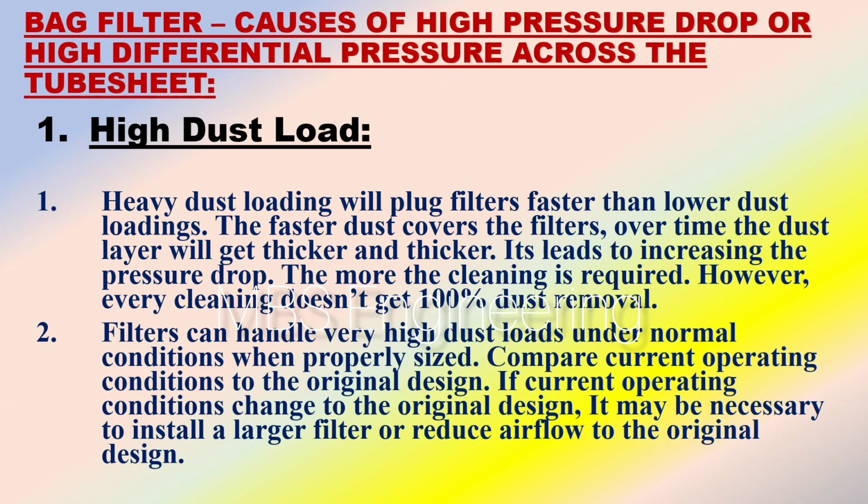One of the main causes of high DP is the high dust load in the gas flow. Point number 1. Heavy dust loading will plug filters faster than lower dust loadings. The faster dust covers the filters, over time the dust layer will get thicker and thicker. It leads to increasing the pressure drop, the more the cleaning is required. However, every cleaning doesn't get 100% dust removal.